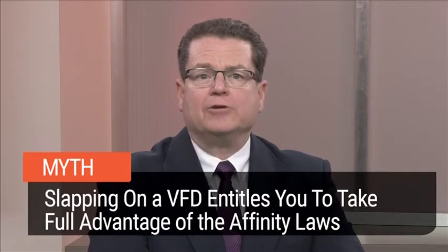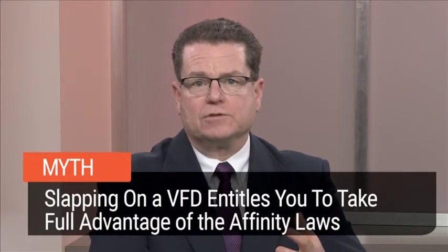Jeannie, I love to study and understand physical principles, and I hate to see them misapplied. In the HVAC industry, the affinity laws are by far the most misapplied of principles. I have to admit that the myth that you slap a VFD onto anything and you get full advantage of the affinity laws is one of my pet peeves.